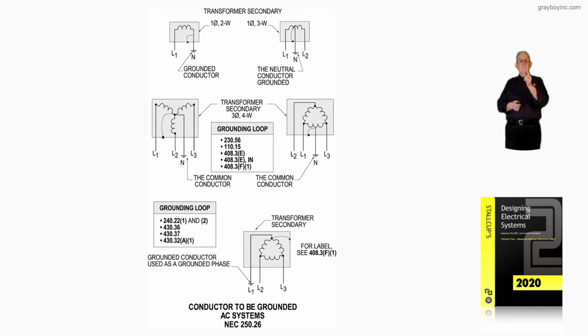And then notice next, if it's service, it's 230.56 because you're service. And then you'd look at 408.3E, 408.3E, informational note, and 408.3F1, it basically says, it's got to be the center. But notice, you only have to identify high leg when the neutral's involved. That's what's important. And if you don't look at all them sections, you might miss that. And you might identify it. You'd say, is that wrong? No. But remember, it has to be the center leg, the B leg, L2. So keep that in mind.